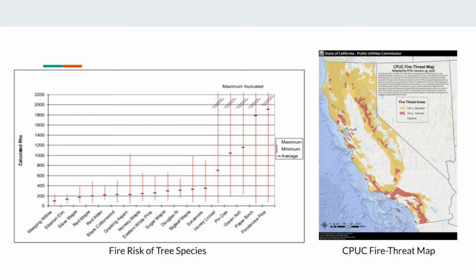Of those 4, the paper birch trees are very common in eastern California, and the ponderosa pine is found in the Coast Range, Cascades, and throughout the Sierra Nevada all the way down to San Diego. The distribution lines in these areas pose a huge fire risk. The most effective solution would be to bury the power lines in high-risk areas. However, doing so can cost up to $5 million per mile and can take several years. Ultrasonic fault detection is a great alternative for adding an extra layer of protection against tree faults in high-risk areas.